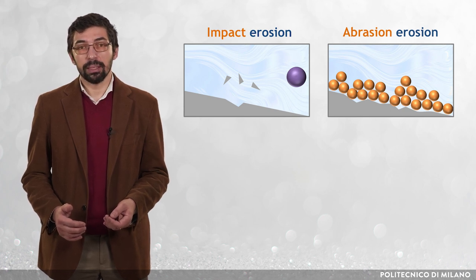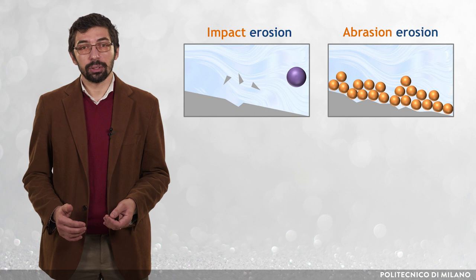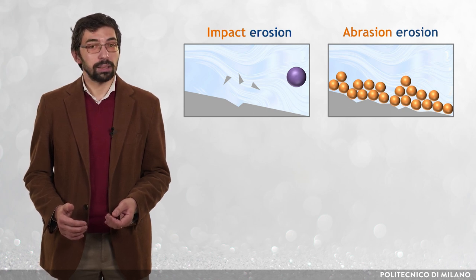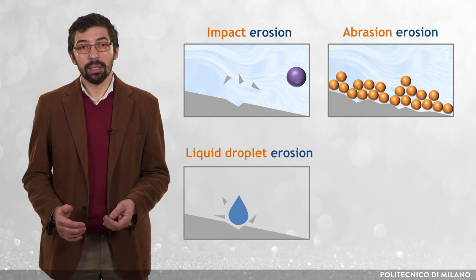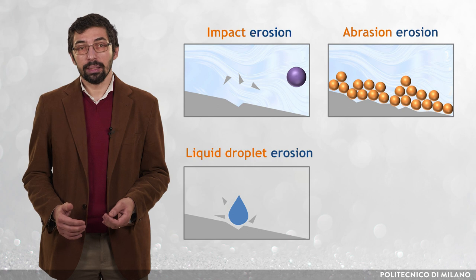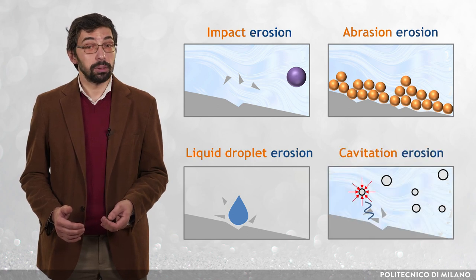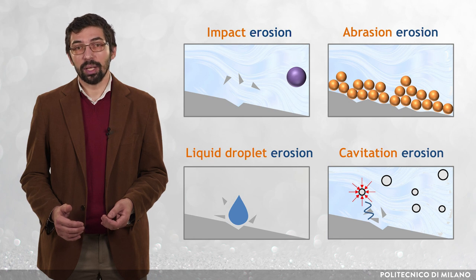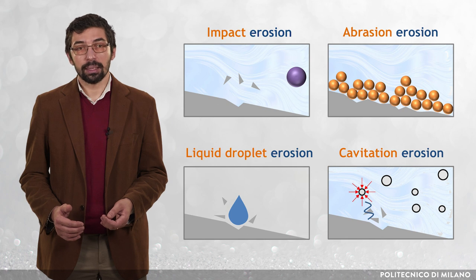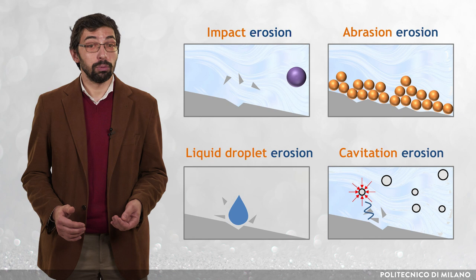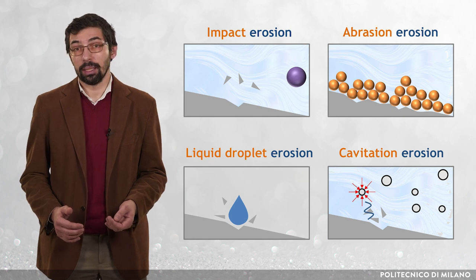For the sake of completeness, it is mentioned that erosion is not necessarily produced by solid particles. For instance, liquid droplet erosion is due to the impingement of high-speed liquid droplets, and it is a cause of failure of steam turbines. Cavitation erosion arises from the pressure wave generated by the collapse of cavitation bubbles, and it is a serious issue in fluid flow machinery, including pumps, water turbines and marine propellers.